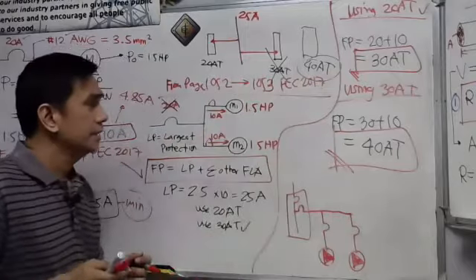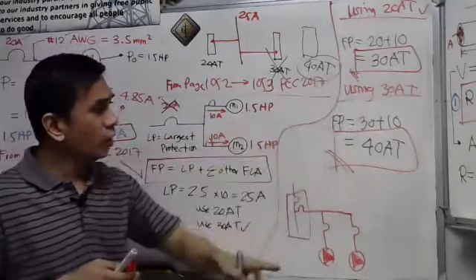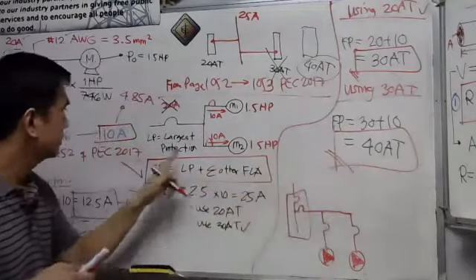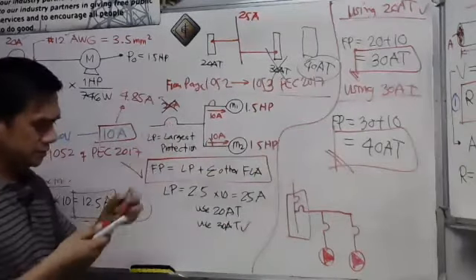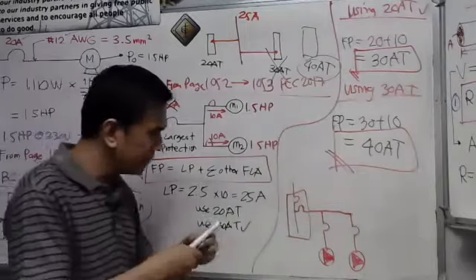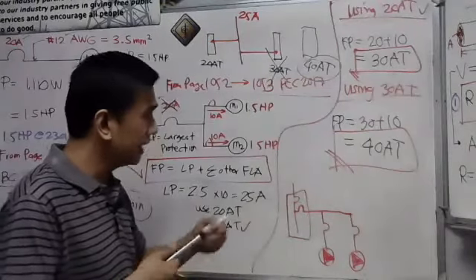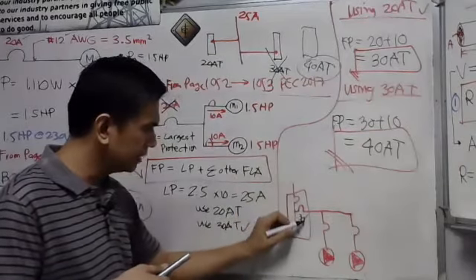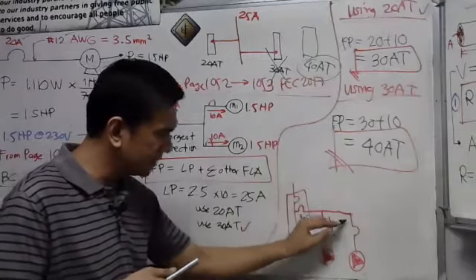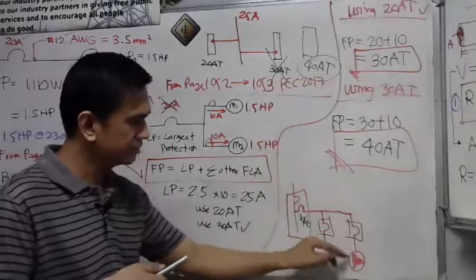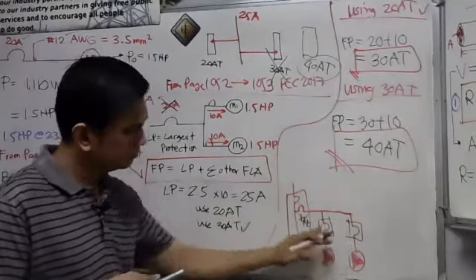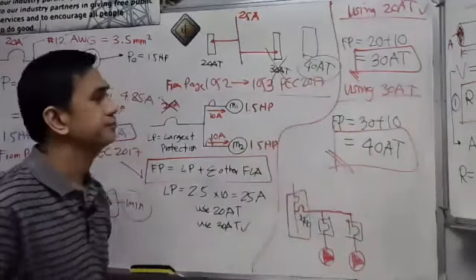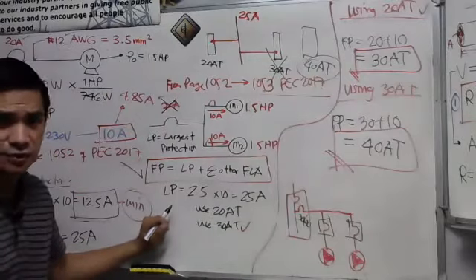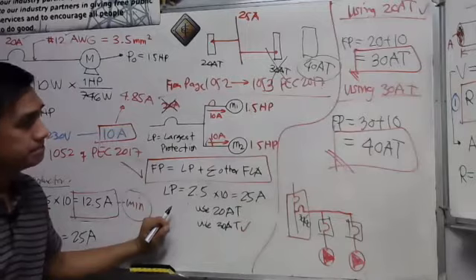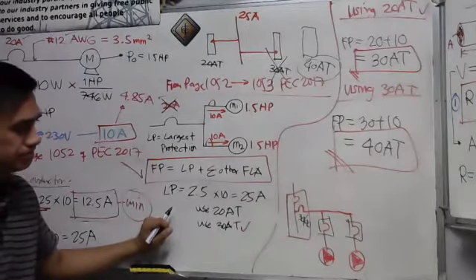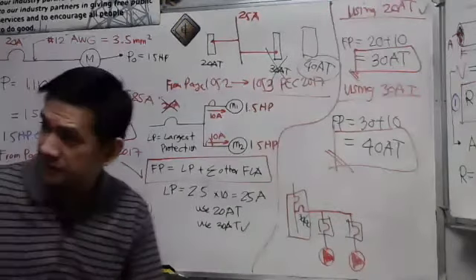So, you can use 30 ampere or 40 ampere here. Use 30 or 40 ampere trip here. Just like here in the panel board, you will put your 30 or 40 ampere here in the panel board, 30 to 40. Because this is an individual, there is a circuit breaker here. Let's say this is a split type aircon or a window type, whatever. So that should be the installation based on the Philippine Electrical Code. Even in the National Electrical Code, they have the same idea here. Okay? So that is my answer to this question.